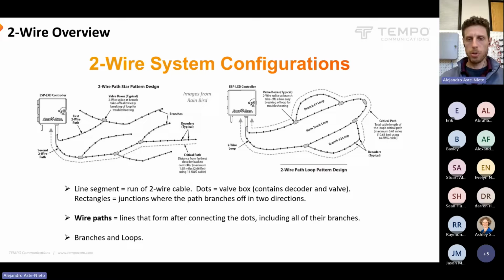And there's pros and cons to doing loops. I think it adds some redundancy, whereas if you have a break, say here, this valve is still connected because it's still got a path back to the controller. And you can get to further distances with loop patterns because there is basically voltage support coming from both directions. But these systems are harder to troubleshoot, so it's recommended to break loops when you're doing troubleshooting, and we'll talk about how to do that.